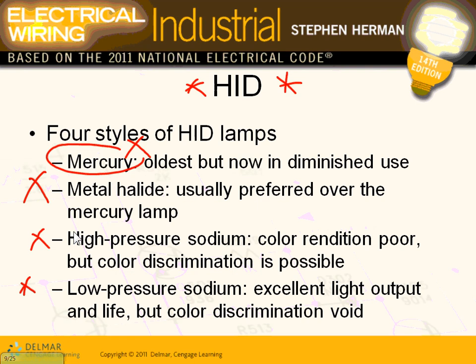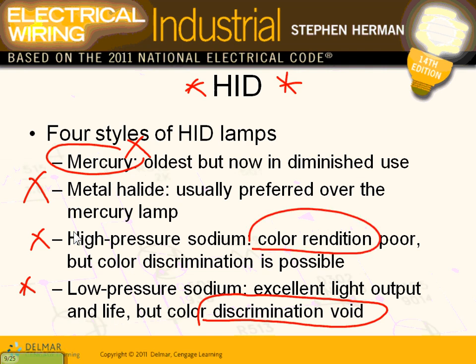The problem with low pressure sodium is that color discrimination is void — no color discrimination whatsoever. Metal halide and high pressure sodium, when treated, can give you good — not excellent, but good — color rendering. Why do I need color rendering? Because I need to be able to find my SUV, my red or black SUV, or whatever color you're looking for.